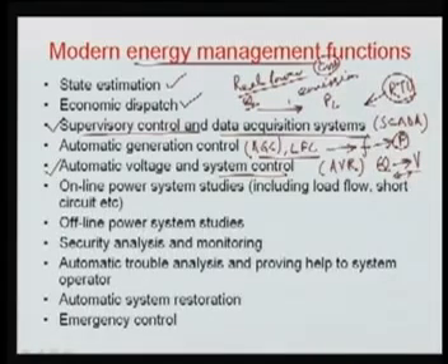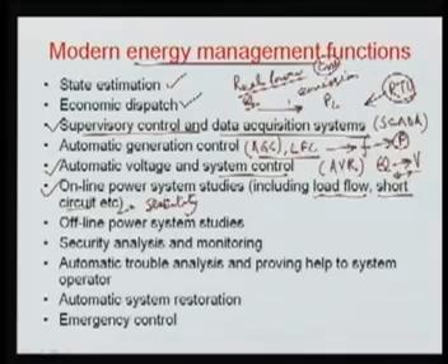Another energy management function is your online power system studies. We require various studies like your load flow, which is very common and very frequently used. Another is your short circuit calculation. We also sometimes require stability studies. So these are your online studies, and those are performed whenever they are required.